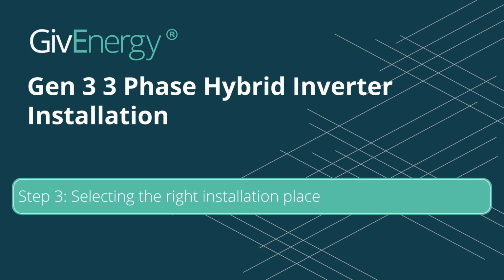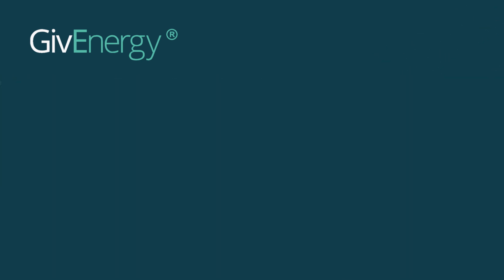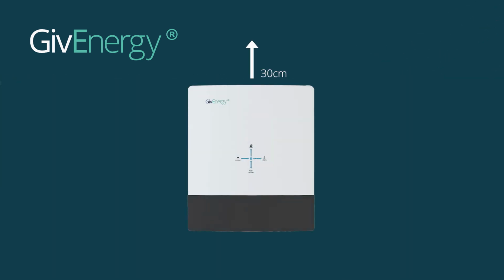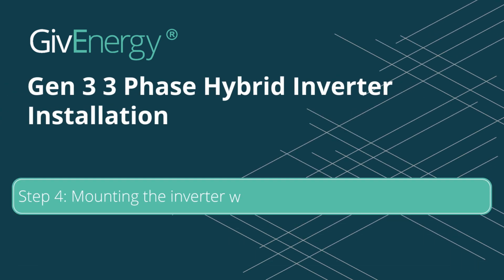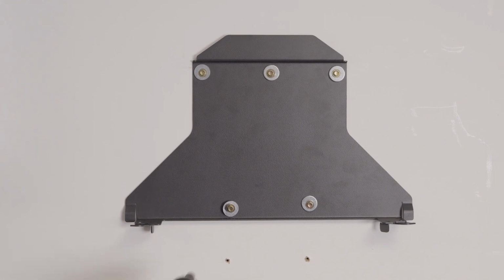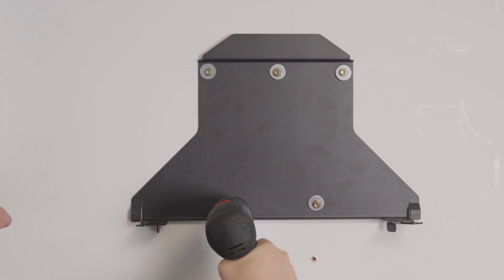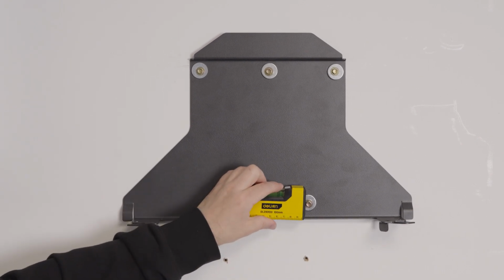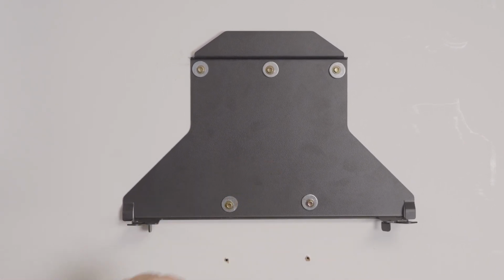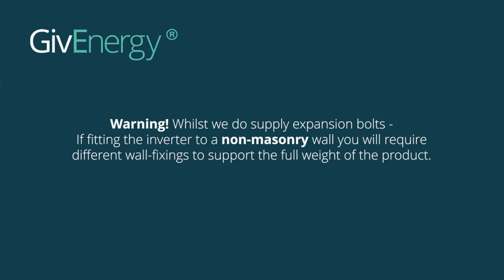Step 3. Selecting the right installation place. There must be 30 cm of unobstructed clearance above the inverter and 25 cm of unobstructed clearance below and to either side of the inverter. Step 4. Mounting the inverter wall bracket. Place the wall mounting bracket onto the wall, remembering to leave adequate clearance to allow for heat dissipation. Fix the mounting bracket to the wall using appropriate fixings. Whilst we do supply expansion bolts, if fitting the inverter to a non-masonry wall, you will require different wall fixings to support the full weight of the product.